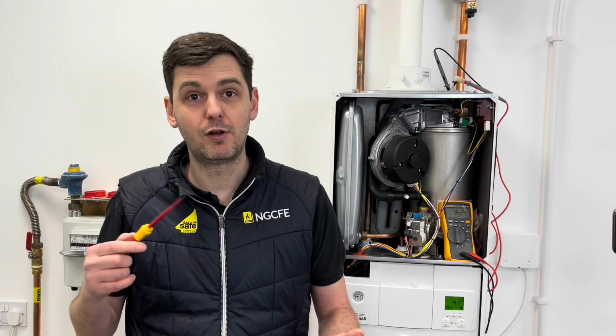If you've got an intermittent fault that's happening further on in the sequence, or while the boiler is operating, that's generally down to maybe an air-gas ratio fault. It could be that the minimum setting is wrong. It could be that you've got a vitiated flame and it's finding it difficult to conduct the voltage through the flame. A multitude of things. But yeah, that's all from me. Thank you very much, and I hope you enjoyed the video and took something from it.